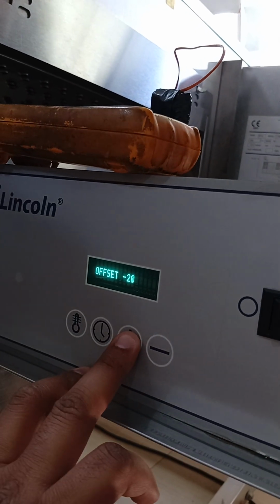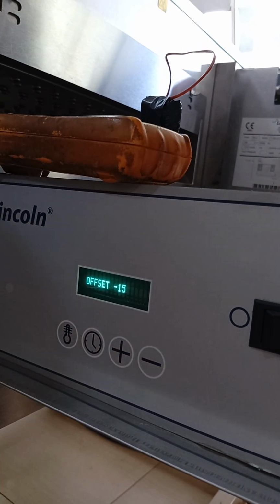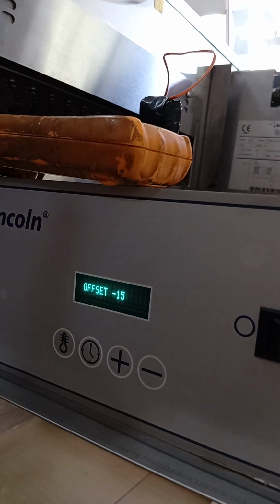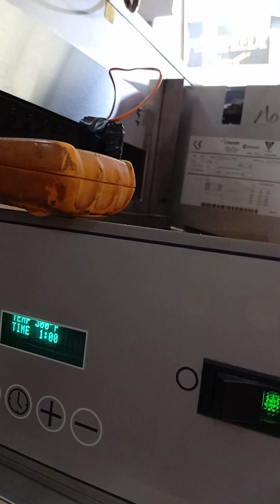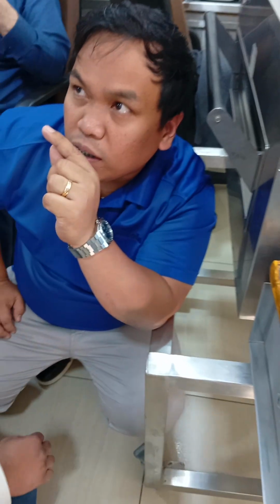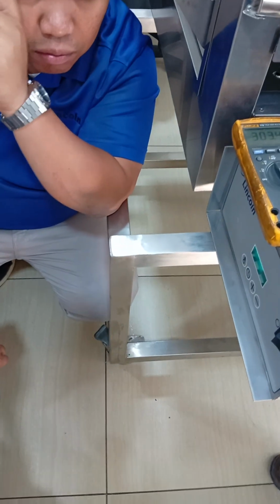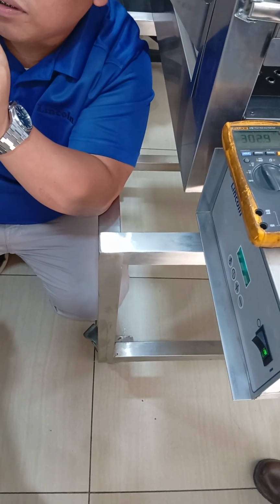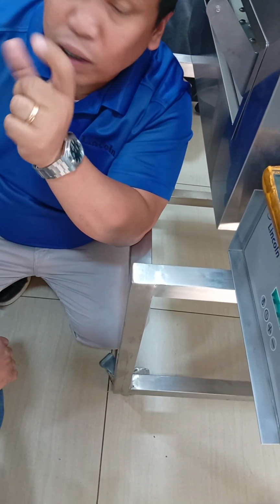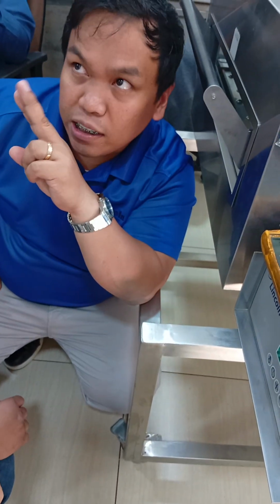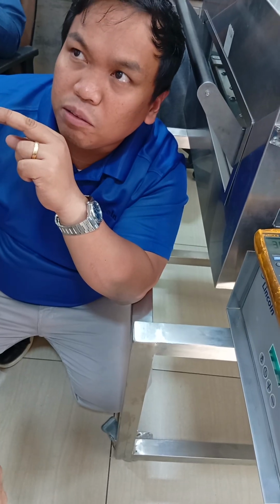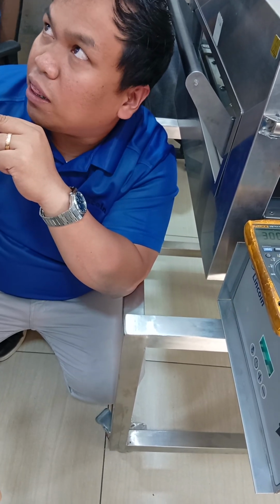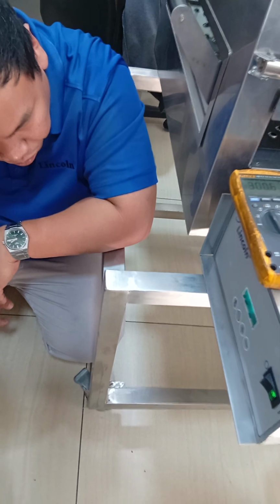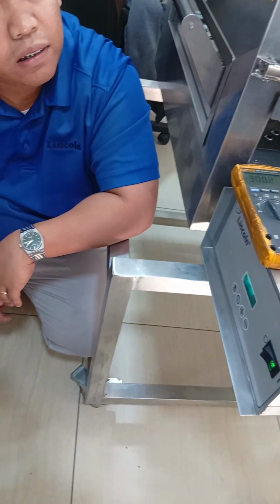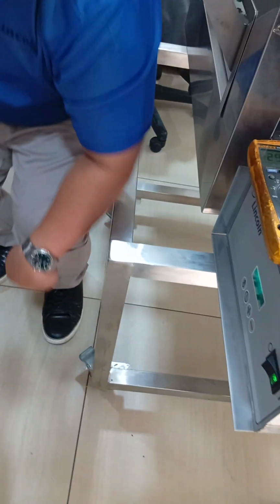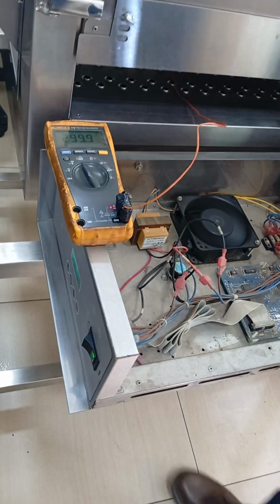At least half of this. So 1 degree of offset is equivalent to 2 degrees of temperature. Double. One degree offset is 2 degrees adjustment. Okay. 15 means 30, double. Yeah, 15 is 30. Okay, let's see.